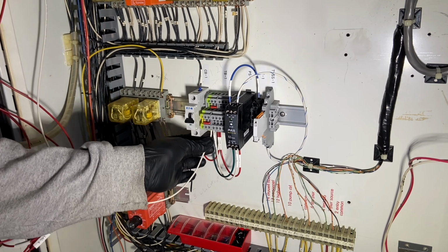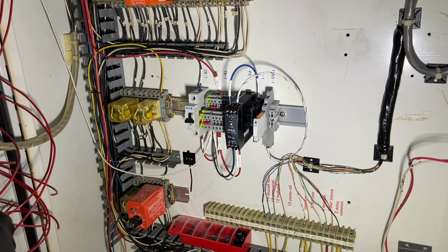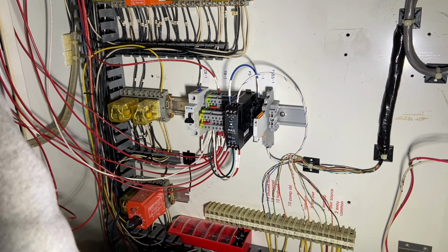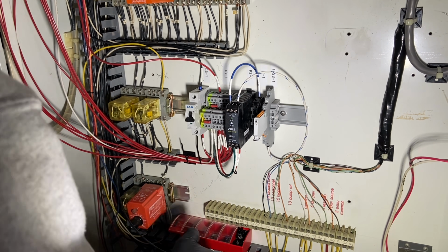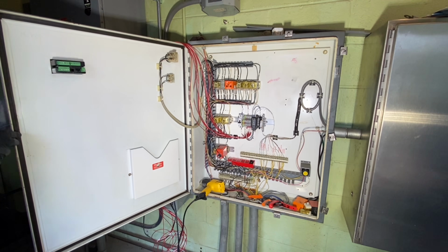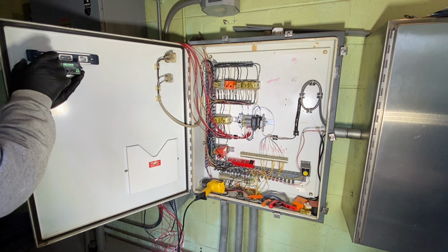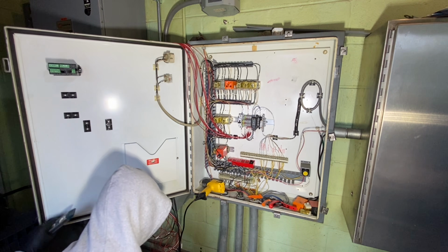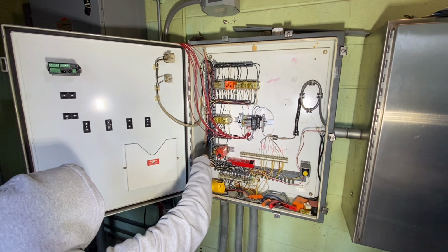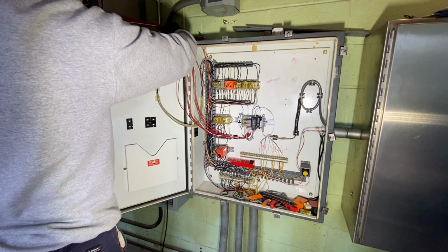So this display is not just a display, obviously, it is also a controller. It is configurable, it has 4 relay outputs, and obviously a milliamp input, which is where our transducer is going to wire into. So this is really what's replacing our floats in terms of actual electrical contacts.